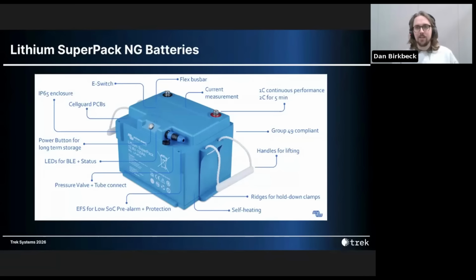On the mechanical side, like the Lithium NG batteries, these include molded ridges for hold-down clamps, so no straps required. There's also a pressure relief safety tube for controlled gas release in extreme fault conditions. This should never be blocked or used for any other purpose. You've got a physical on-off push button that disables both charging and discharging. When switched off, the battery enters storage mode with less than 3% self-discharge per month. And finally, two built-in LEDs give you status for Bluetooth, warnings or alarms, and firmware updates.